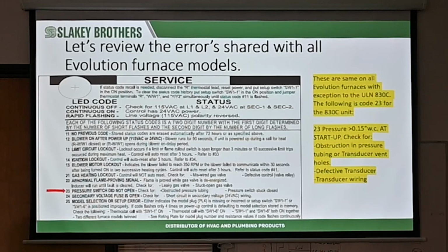I think it's going to be in my schematic, but that little model chip is just some resistors. The resistors basically tell the furnace what size it is. That's it. Those resistors very, very rarely go out. If you get a code 25, there are 4 connection points. On the door of the unit, it tells you, or you can call us, I don't have it off the top of my memory, but you check two connections for a certain resistance, and you look at the other 2 connections for a certain resistance. If you don't have that resistance, then that little chip is bad. Very rarely does that happen.